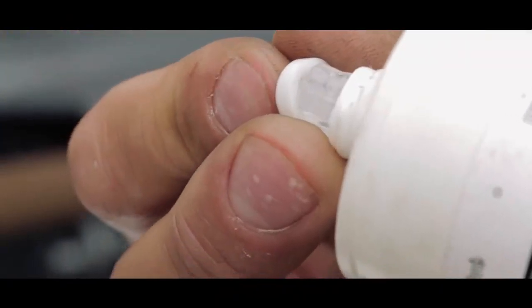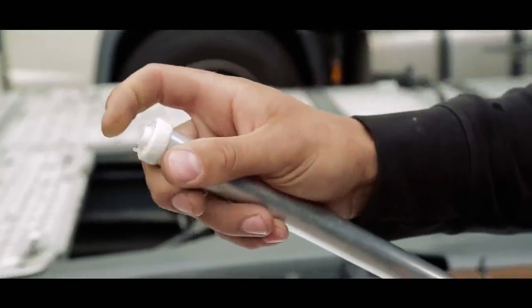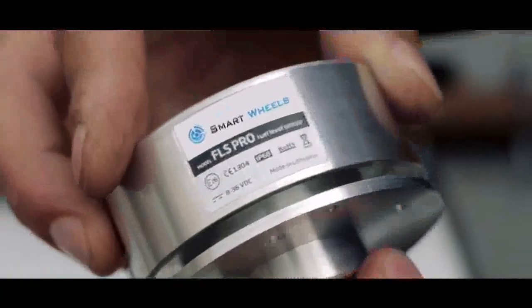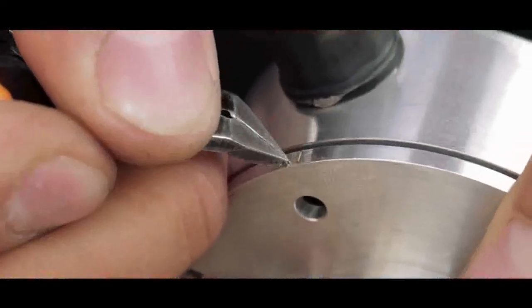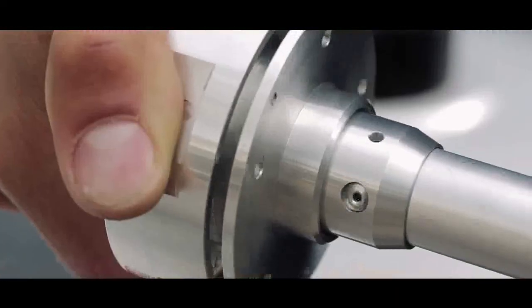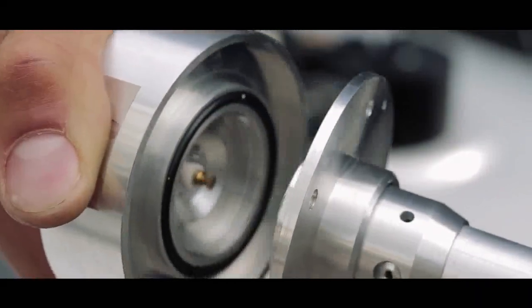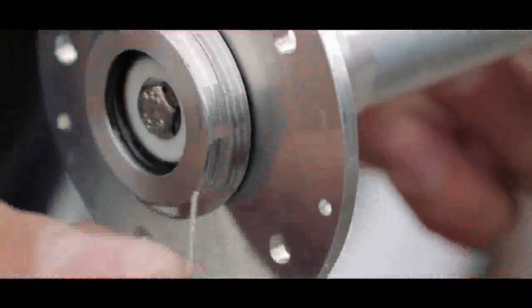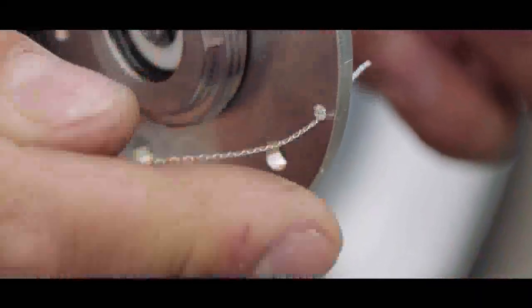Put a dash of auto sealant on the smaller white cap and put it in the place where the wire is wrapped up. Place the fuel level sensor head on and mark an area on the flange where the wires go out. Then, take the fuel level sensor head off, find a smaller hole near the marked place, and put the wire through it for seal.